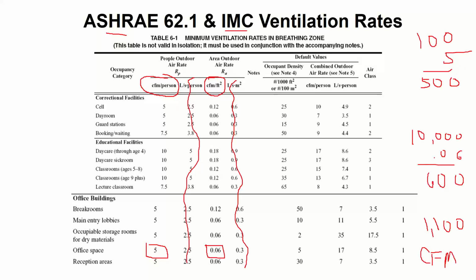Now, the main air handling system may do, let's say, 10,000 CFM. And I need to get 1,100 from outside. So that's 11% outside air in that example, which means 89% of it can be recirculated, right? If I only had a 5,000 CFM system, okay, great. Then that means I have 22% of it coming from the outdoors, right? Which means I have 78% of it being recirculated, and so on. I take the amount of air I need per person and multiply that out, and the amount of air I need per square foot and multiply that out, and then I add the two together.